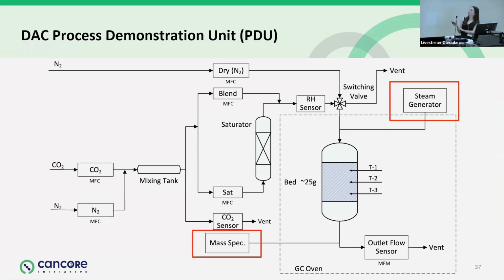In addition, these are probably the heart and soul of this instrument. So we have our steam generator here. It is instrumental in being able to basically meter steam well, and we've had to build an in-house steam generator because the commercial products that we've tried have not been able to do the job. Because we want to study a range of steam flows, which means you need to be able to look at very low and high steam flows without basically having two-phase flow, which is quite difficult to do.